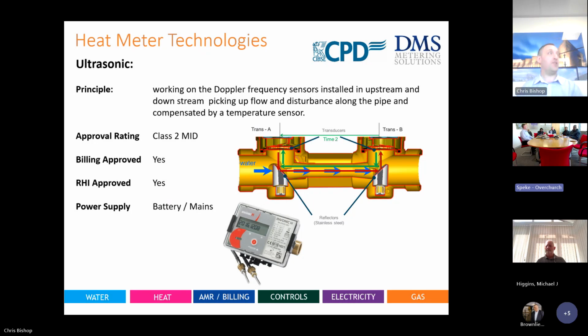So the meter would know, based on its circumference and its bounce or the speed, the actual velocity of that water at that time. If it's a lot slower, the opposite happens: a slower flow rate, a slower bounce back, and that's the actual design. Ultrasonics can be used for class 2 billing by far. Anything HIU, anything RHI, anything heat pump related, anything with a billing request, a district heating request, no problem at all. That is one option.